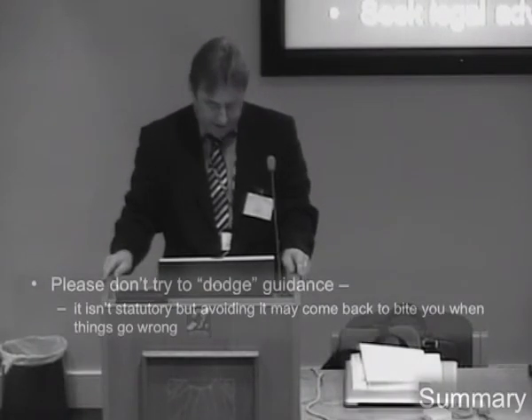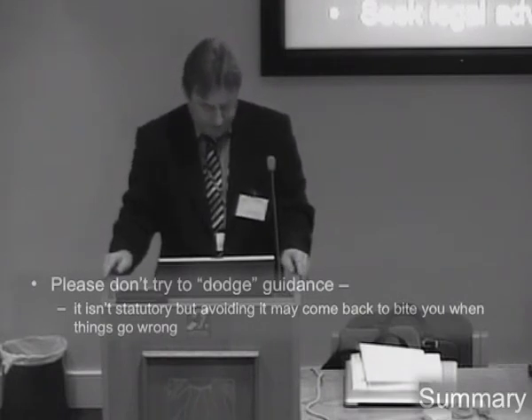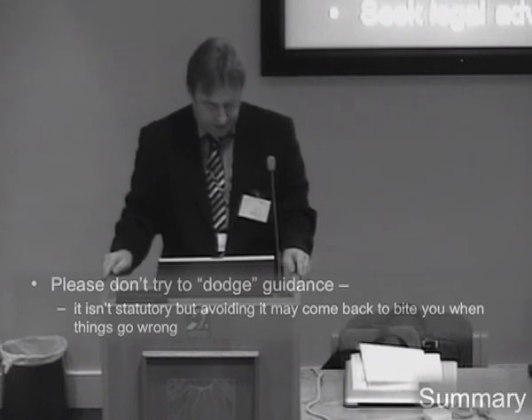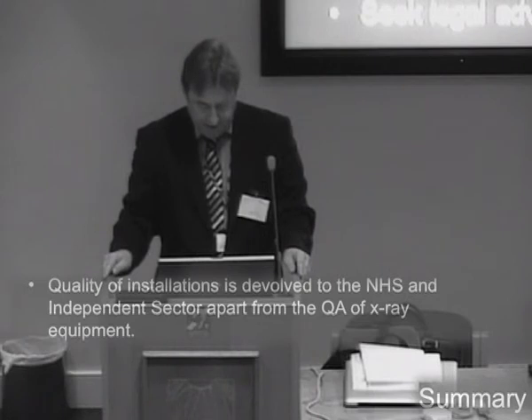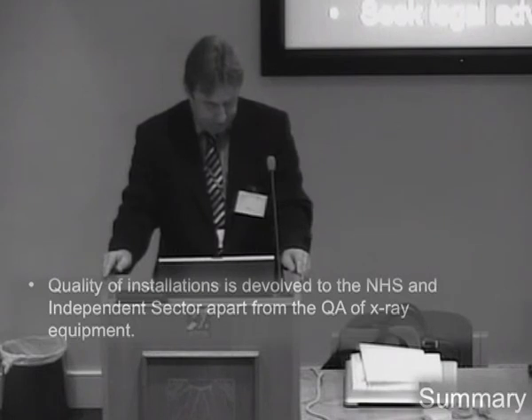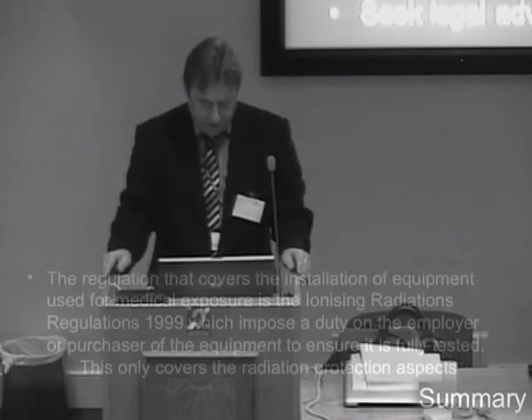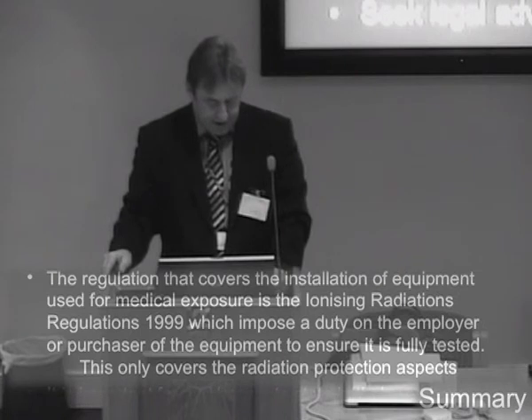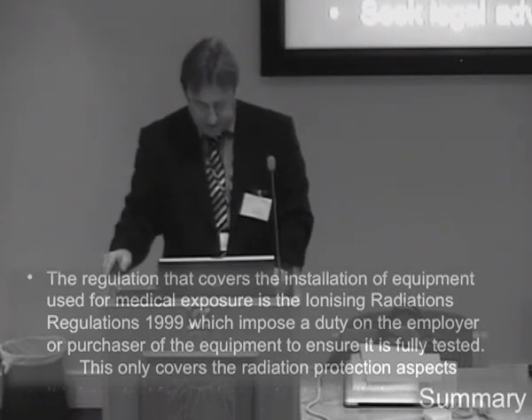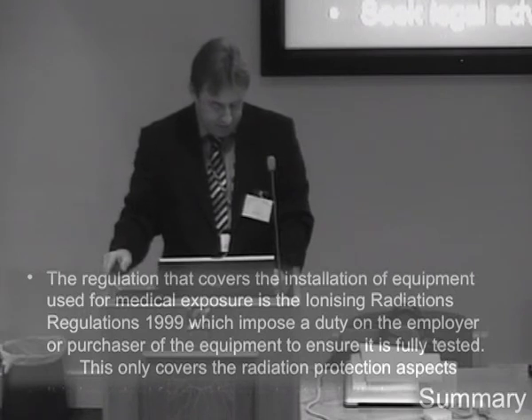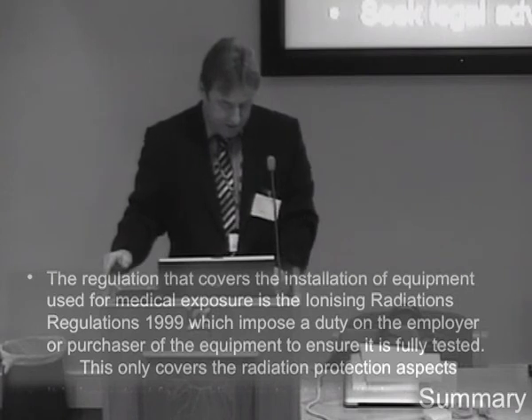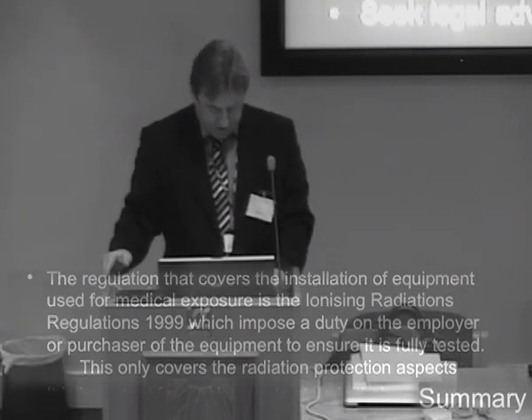So, in summary, please don't try to dodge guidance. It isn't statutory, we know, but avoiding it may come back to bite you when things go wrong. Quality of installations is devolved to the NHS now and the independent sector, apart from the quality assurance of the X-ray equipment. The regulation that covers the installation of equipment used for medical exposure is the Ionising Radiations Regulations 1999, which impose a duty on the employer or purchaser of the equipment to ensure it is fully tested, but this only covers the radiation protection aspects.